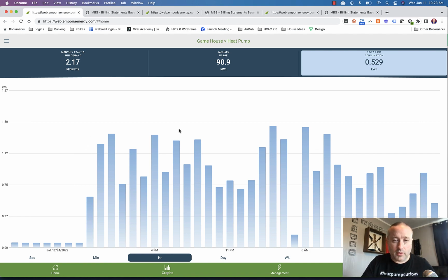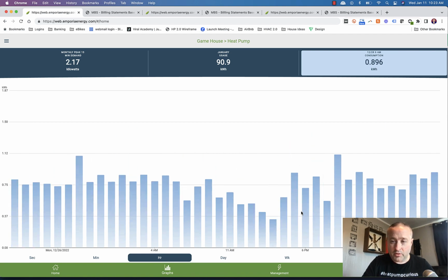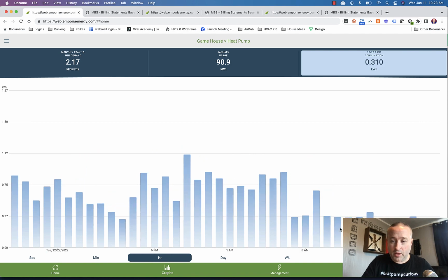So every day or every hour here is 1.5 kilowatt hours or so. So that is what the heat pump was doing through there, and it stayed cold through Christmas basically. And then you can see it got warm just after Christmas, and see that the usage per hour dropped to under 0.4. So not very much. And the max that this can pull is about 1.5 kilowatt hours per hour, somewhere in that range. Okay, so let's go look at the resistance for this period.